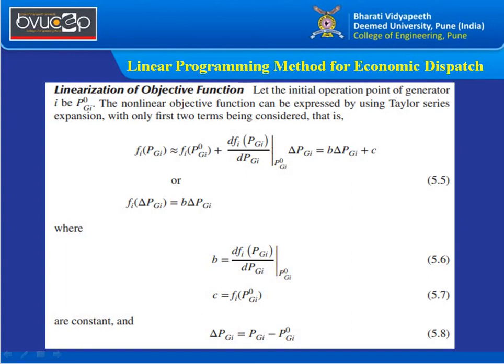Now for the linear programming method: since the objective function is non-linear, we linearize it. Given an initial operating point Pgi0, using Taylor series expansion, the function fi(Pgi) ≈ fi(Pgi0) + (dfi/dPgi)|Pgi0 · ΔPgi, expressed in terms of constants b and c. The incremental variable is ΔPgi = Pgi − Pgi0, the difference between the current value and the initial operating point.